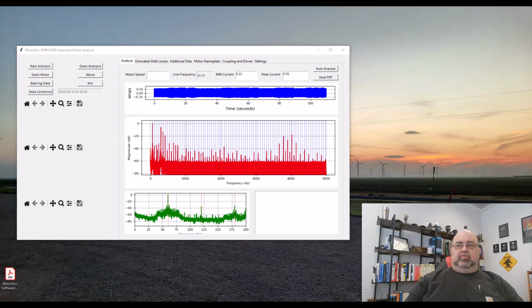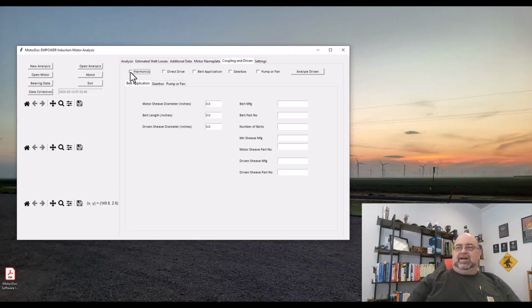Okay, so the ground lead, on the other hand, this is what it looks like. Some additional noise, looking closer to what is on the machine. That's because all of the ground noise, of a relatively low current, is being induced into it. Now, mind you, the motor itself is only drawing about 2 to 3 amps, so this is actually a fair amount of current for that. But it's feeding right back, and that's what the drive is referencing. Let's take a look and see what the harmonics look like.